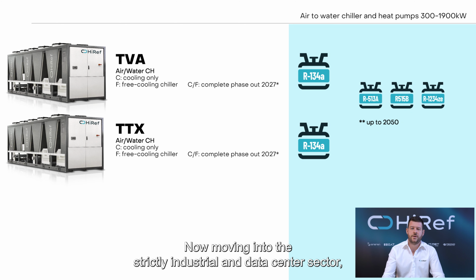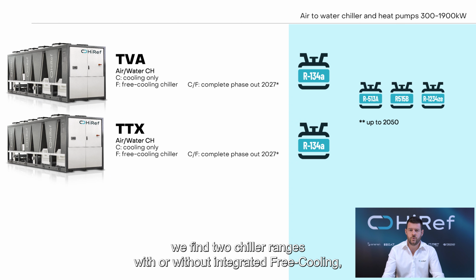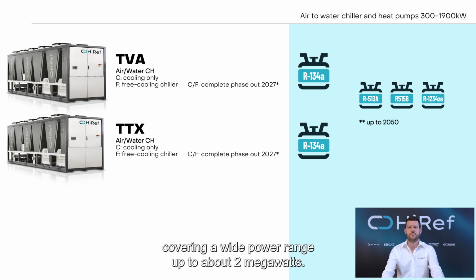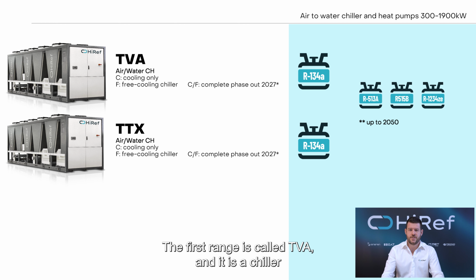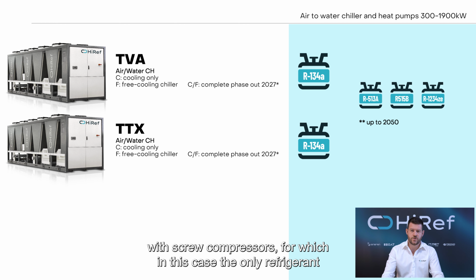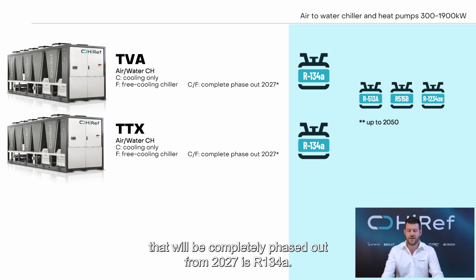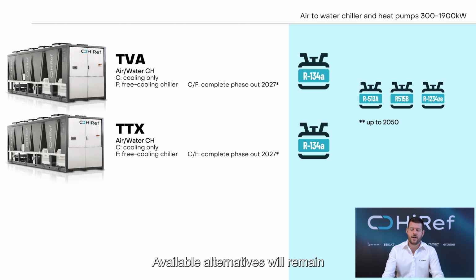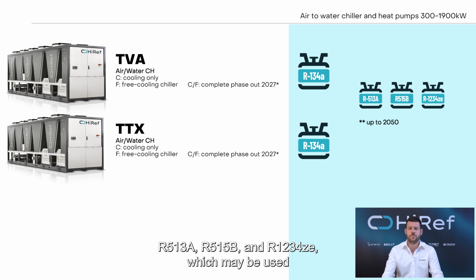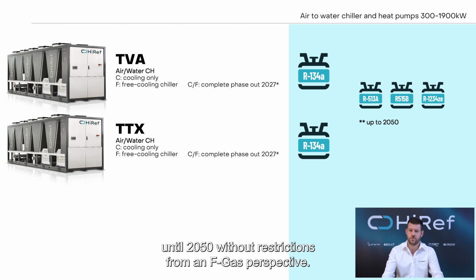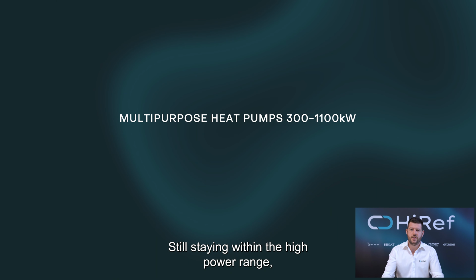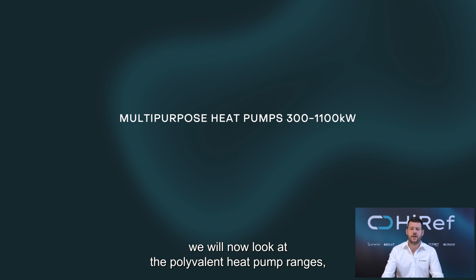Now moving into the strictly industrial and data center sector, we will find two chiller ranges with or without integrated free cooling, covering a wide power range up to about 2 megawatts. The first range is called TVA, and it is a chiller with screw compressor, for which in this case the only refrigerant that will be completely phased out from 2027 is R134A. Available alternatives will remain, such as 513A, 515B and 1234ze, which may be used until 2050 without restriction from an F-gas perspective. Still staying within the high power range, we will now look at the polyvalent heat pump ranges.